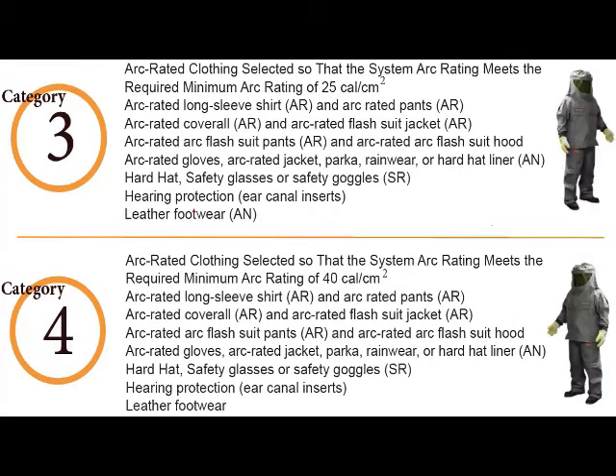Categories 3 and 4 are considered secondary PPE, meaning we have to go with another layer. Here the incident energy rating will be 25 calorie for category 3 and 40 calorie for category 4.